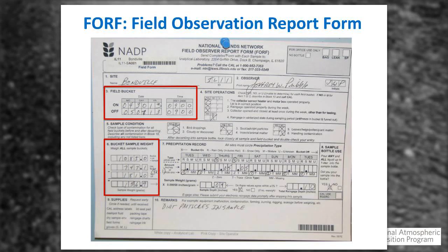We have an issue. We ask operators in a timely fashion, once in a blue moon, to do a check of their scales. Check the scales on an annual basis, make sure that they're zeroed out and cleaned and are accurate in their weighing of the bucket and lid and sample to give us an accurate total volume.